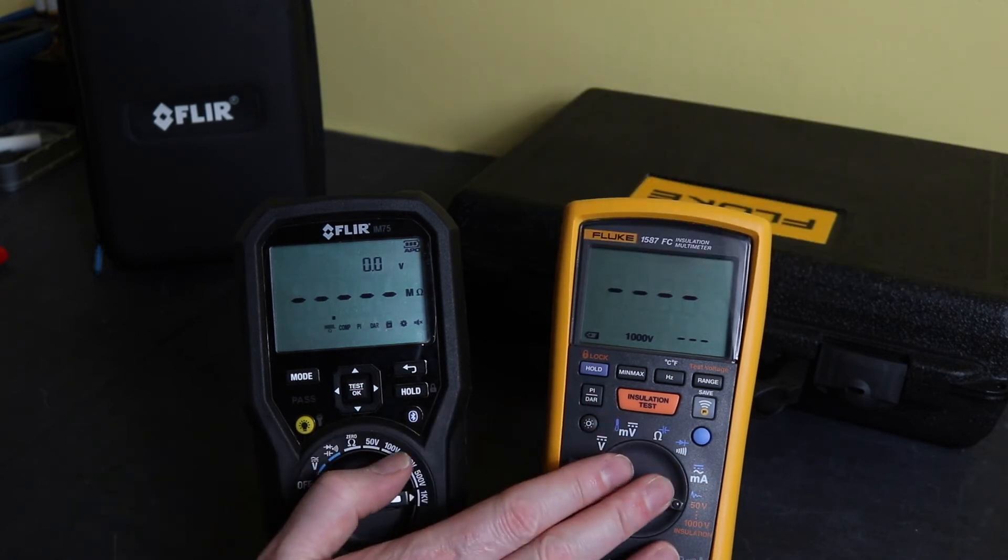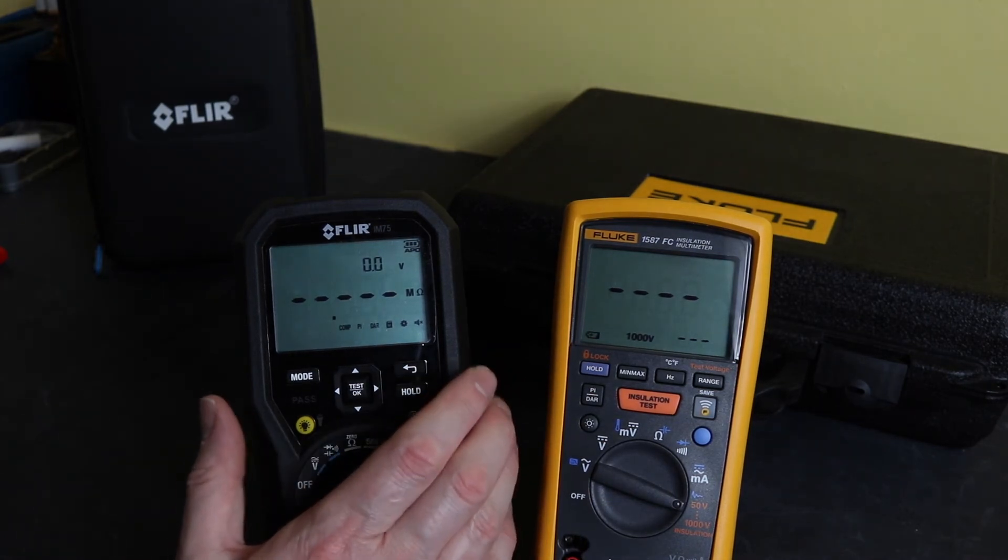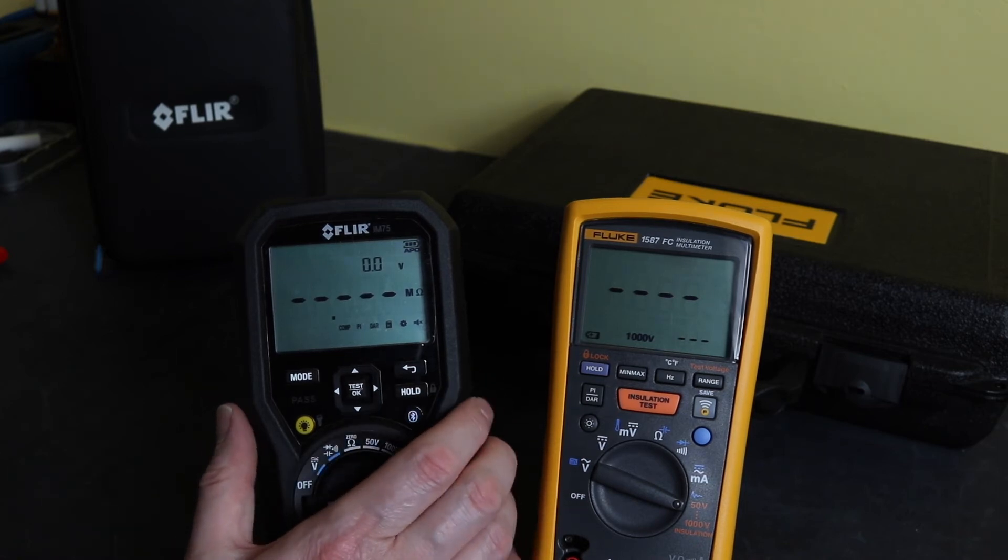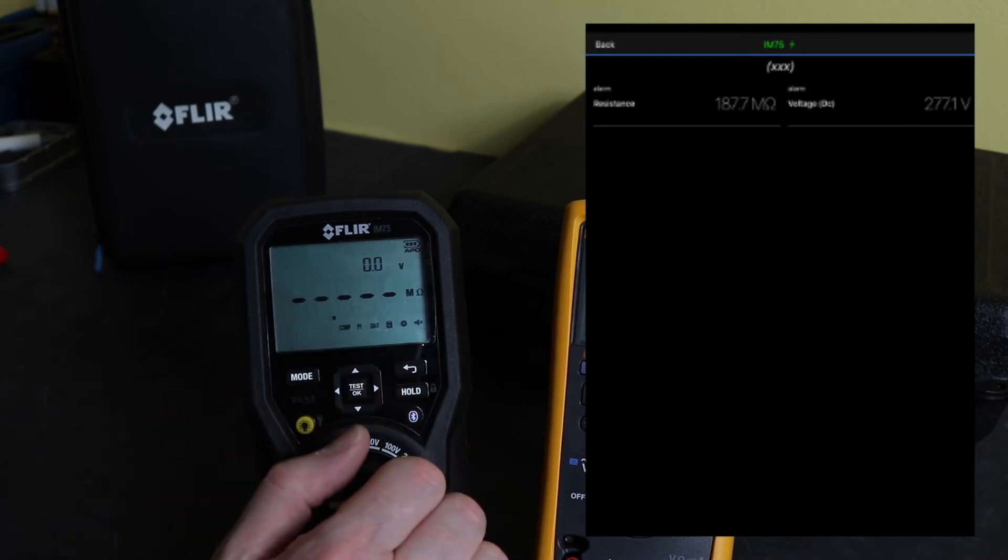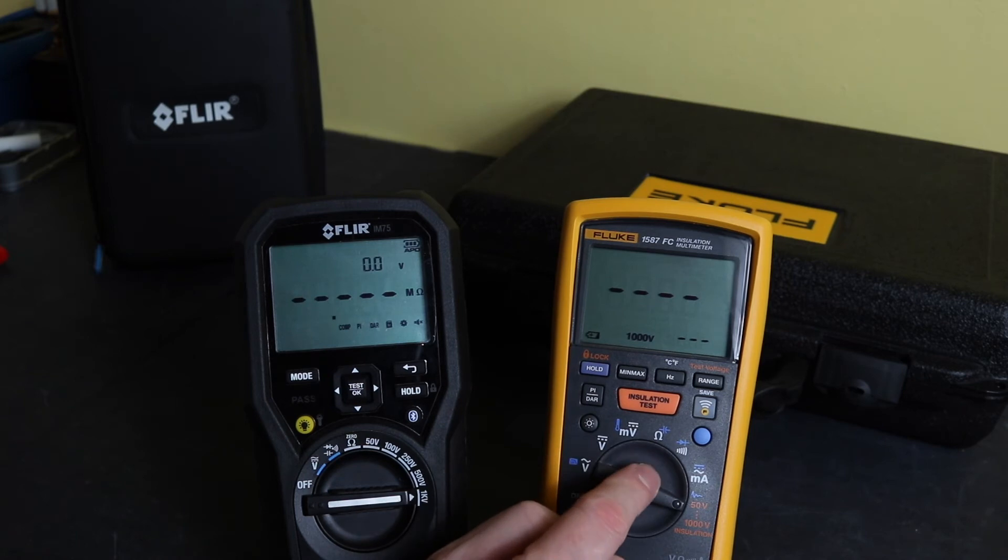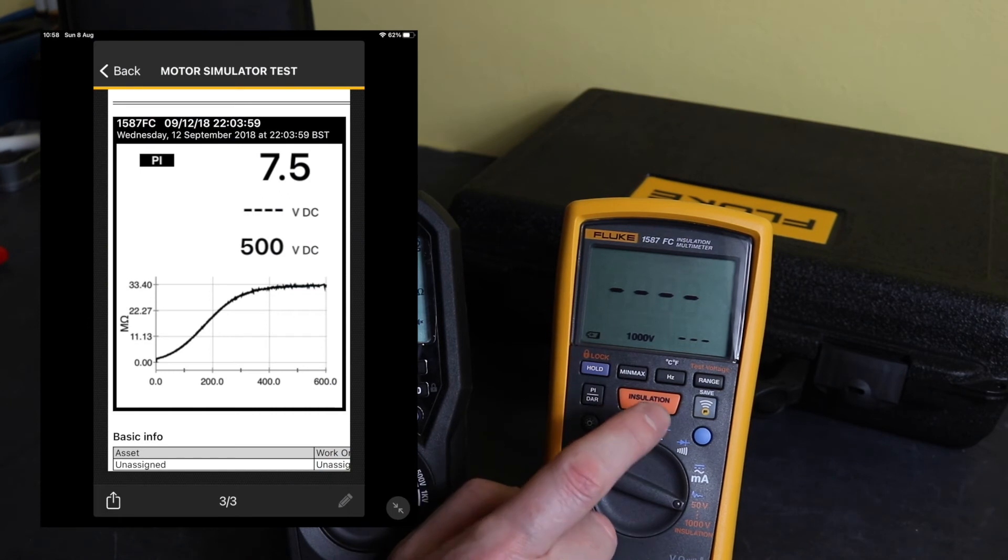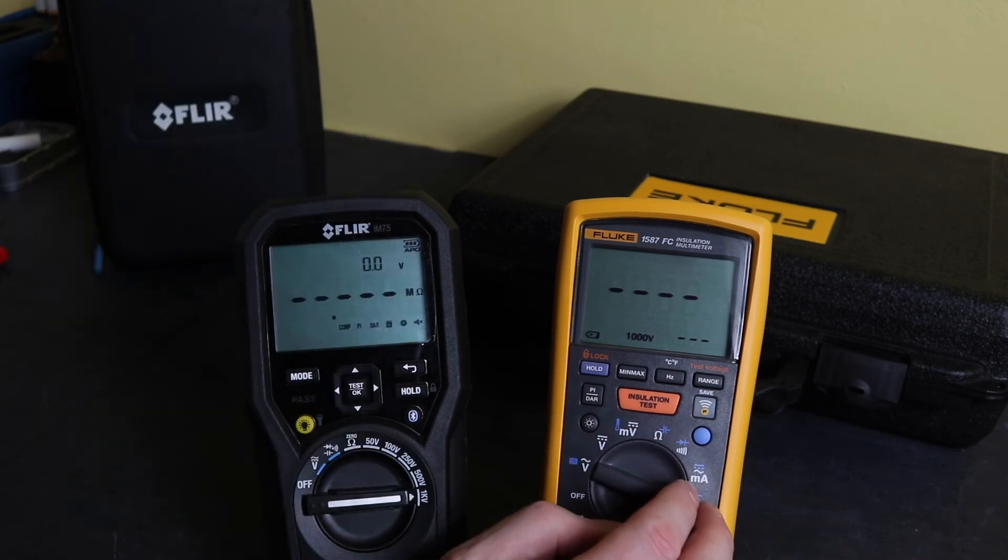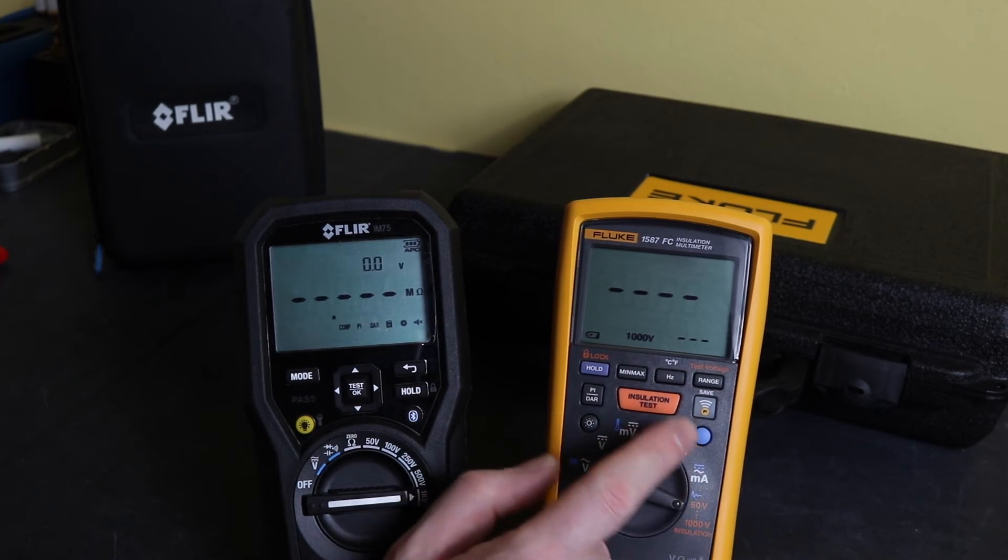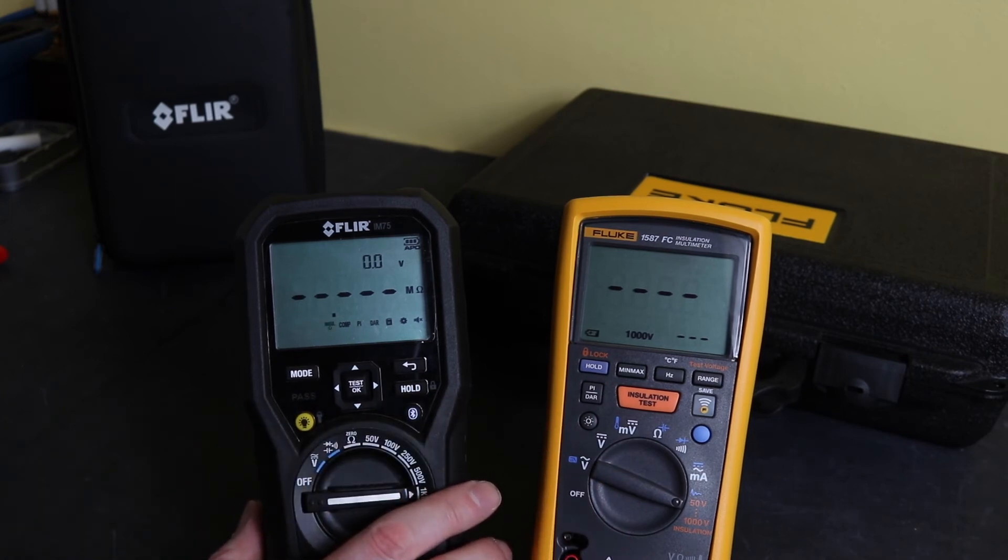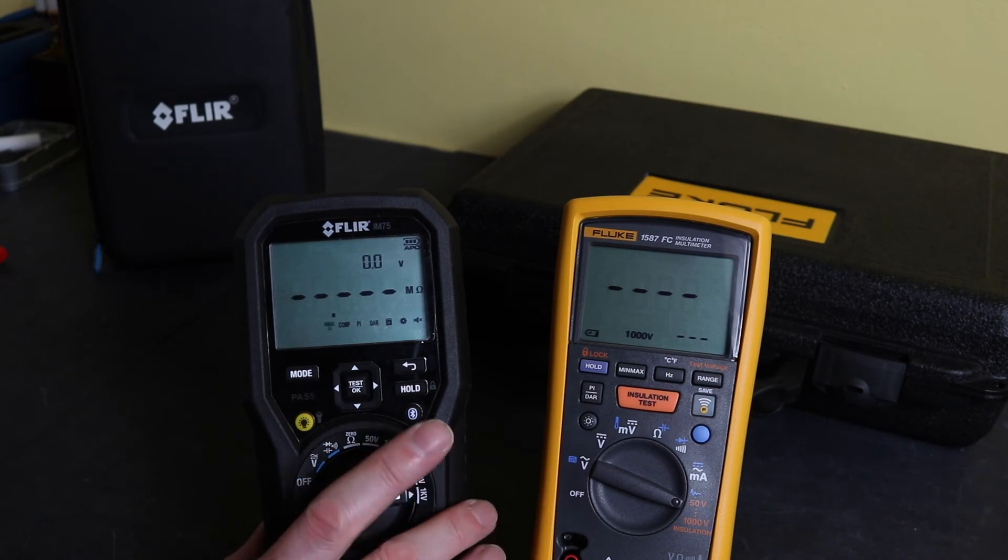Both instruments do have Bluetooth capability. The Flir will talk to the iPad. I have actually checked and I do have the latest software loaded. To be honest, direct connection to the iPad I don't find to be very useful. It's very limited, just really screenshots of the reading that's on there. For the Fluke you do have Fluke Connect and you can record a DAR and a PI test and get the plot out. You can make a little mini report out of that and put some pictures in there of the motor that you've tested or cable or whatever it is that you've tested and combine it with any of the other functions. The Flir just doesn't have that kind of capability in its software.